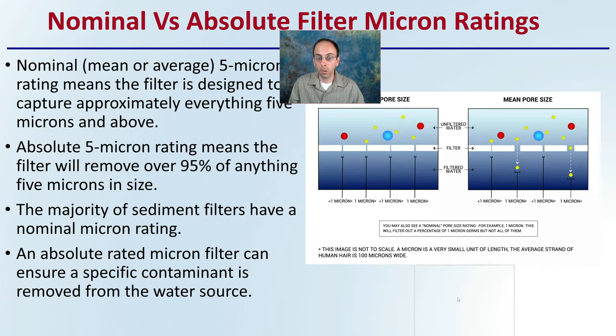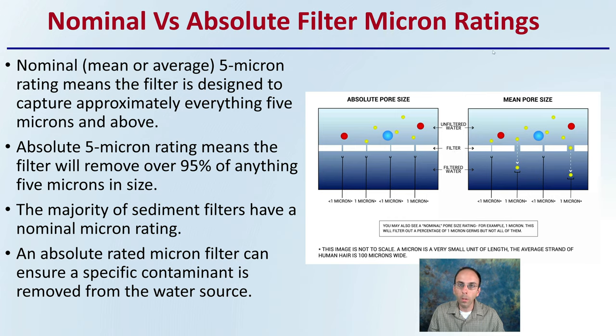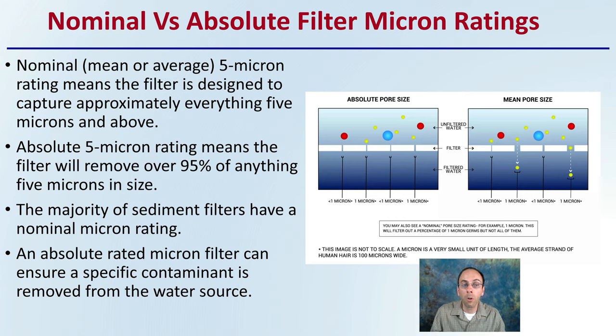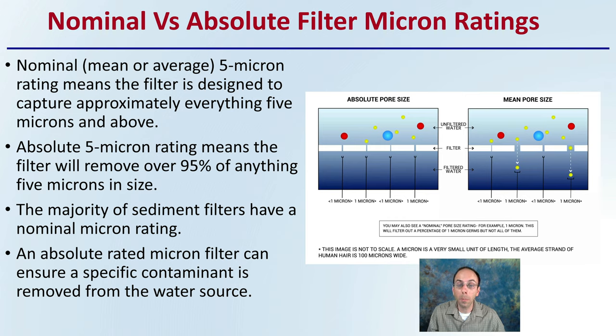Nominal versus absolute filter ratings are often used as interchangeable terms, but they are not. A nominal — or average — 5-micron rating means the filter is designed to capture approximately everything 5 microns and above. An absolute 5-micron rating means the filter will remove over 95% of anything 5 microns in size. Keep in mind that nominal versus absolute will likely have a significant price difference, as an absolute-rated filter ensures a specific contaminant is removed and costs more for that precision.